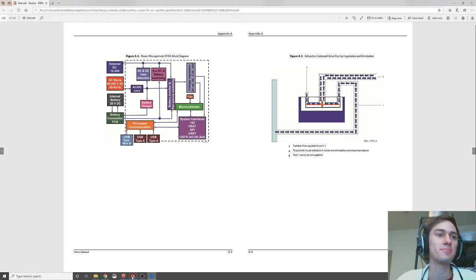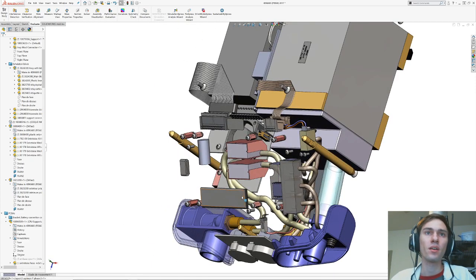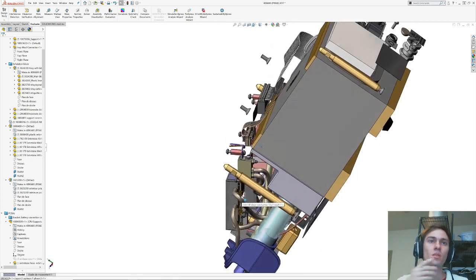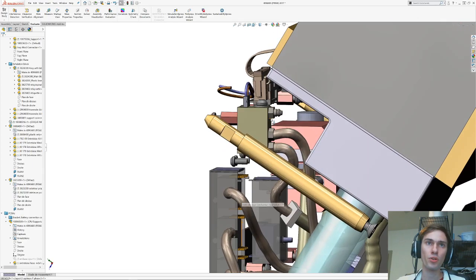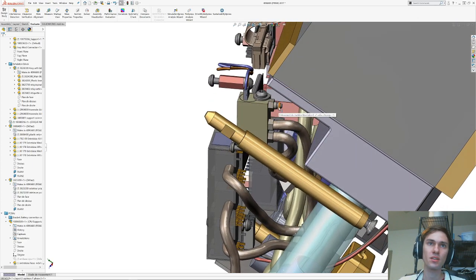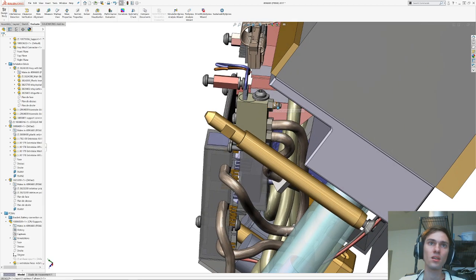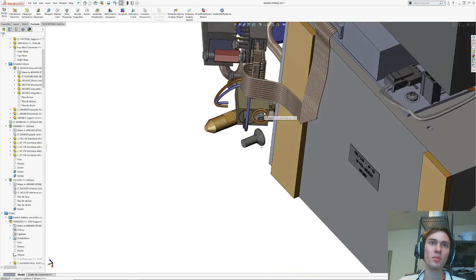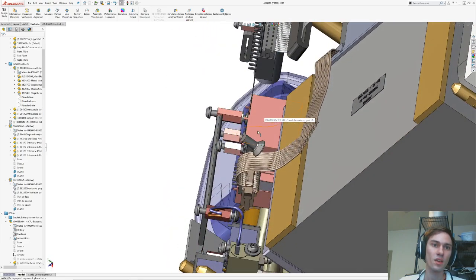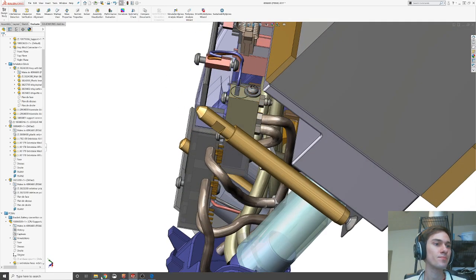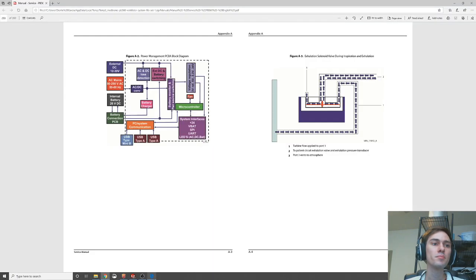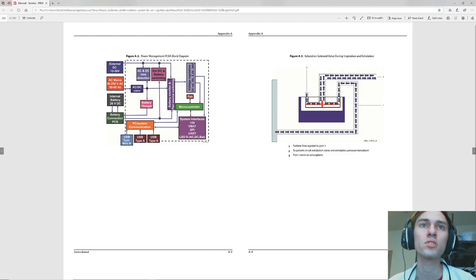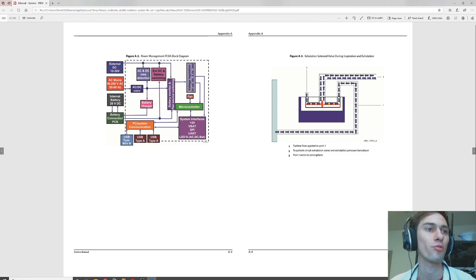So if we go back to the CAD and we're looking here, this is going to be port 3 right here. It vents to atmosphere. Is there any labeling on it? No, it doesn't look like there's any labeling on it. Okay, so that's port 3. That's going to vent to atmosphere. Port 2 connects to the patient circuit exhalation valve and exhalation pressure transducer. And port 1 is turbine flow.